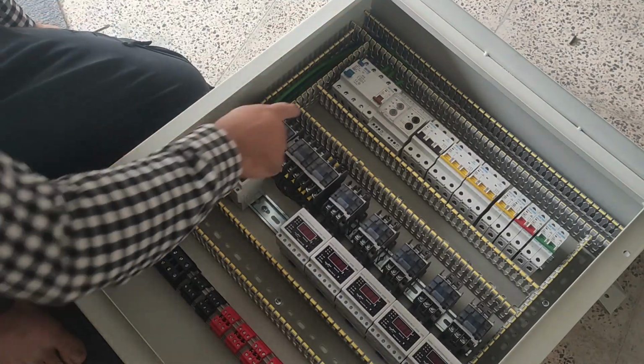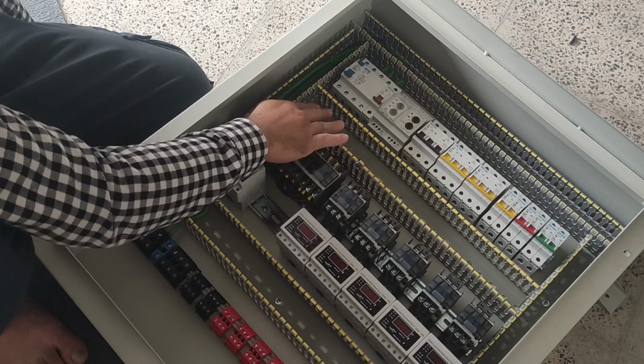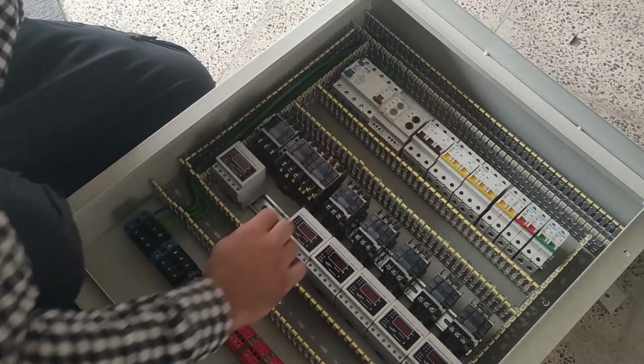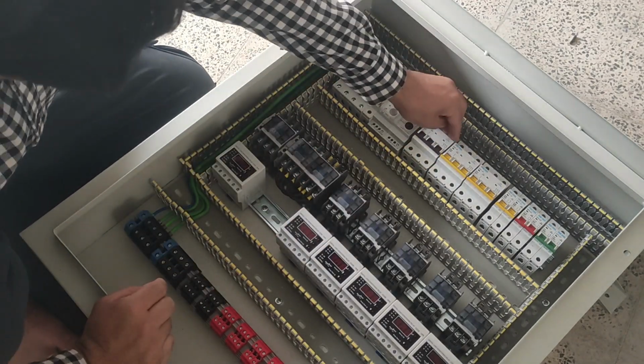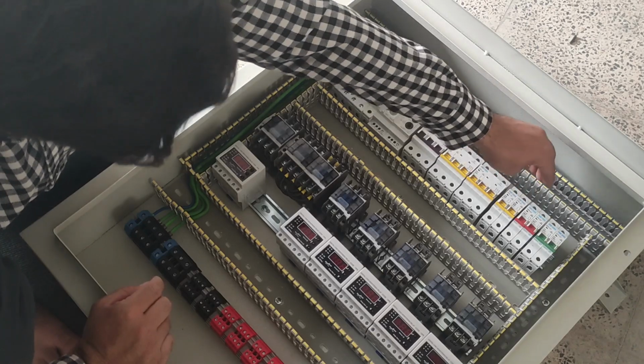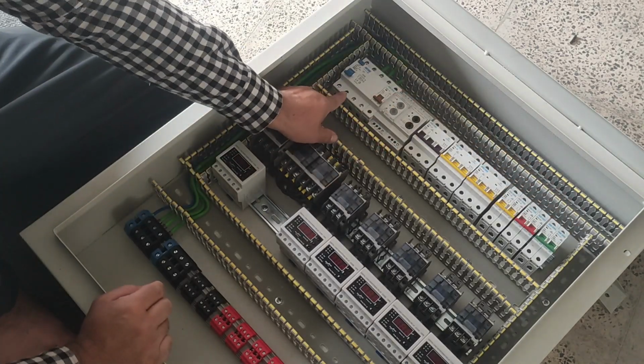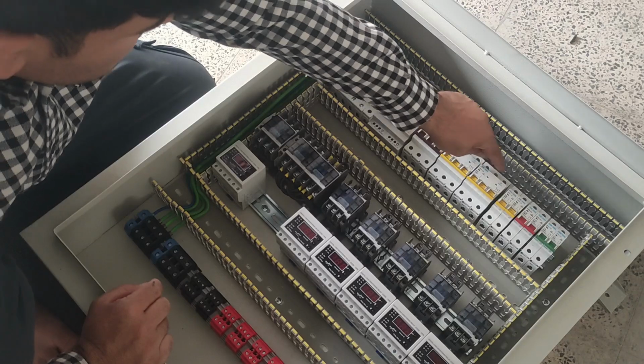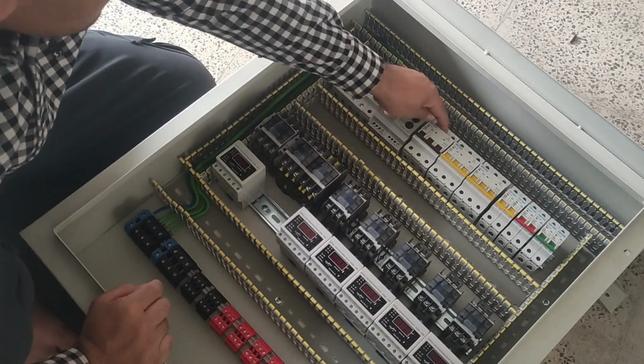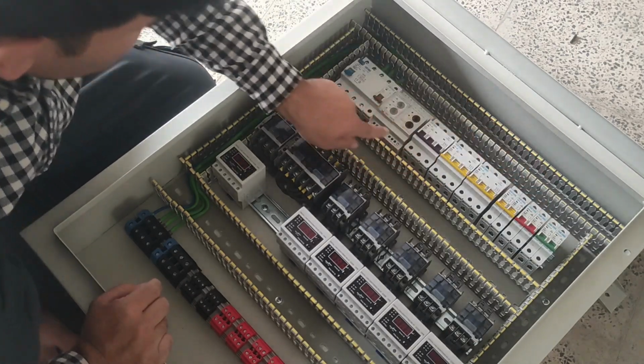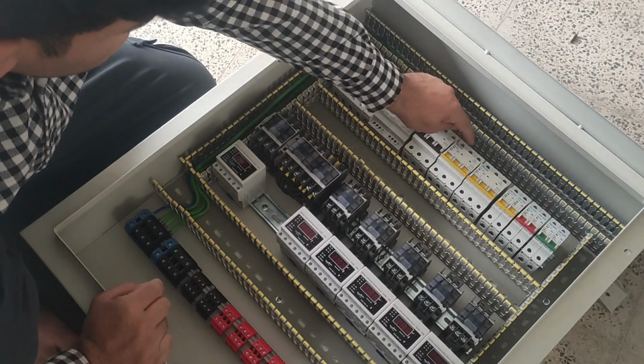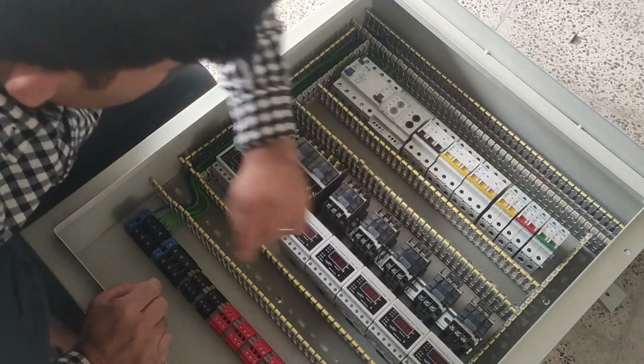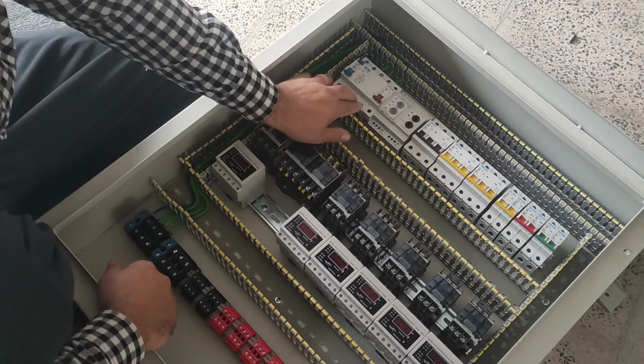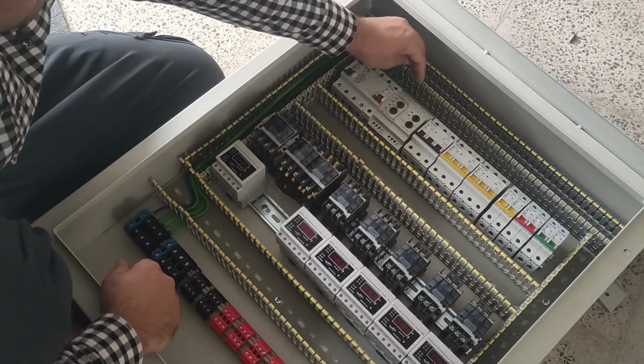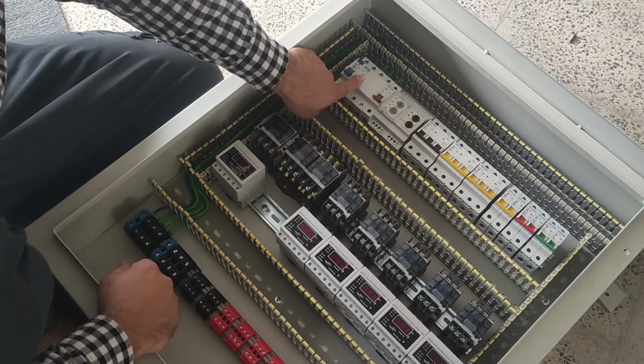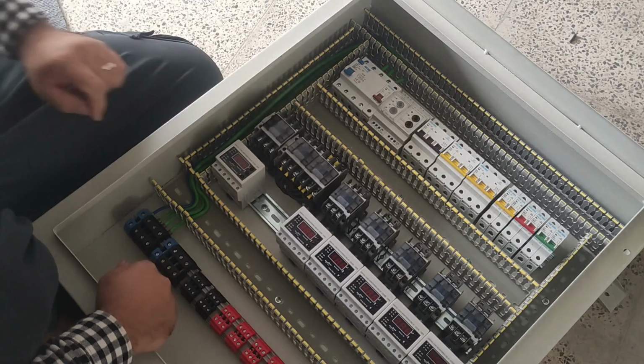Now we connect the three-phase wires from the output of the RCCB switch to the input of the three-phase and single-phase miniature switches. By doing this, all the desired switches are organized and each of them supplies electricity to a part of the board. Also, to control the phases voltage, we connect the three-phase wires from the output of the RCCB switch to the phase controller relay.